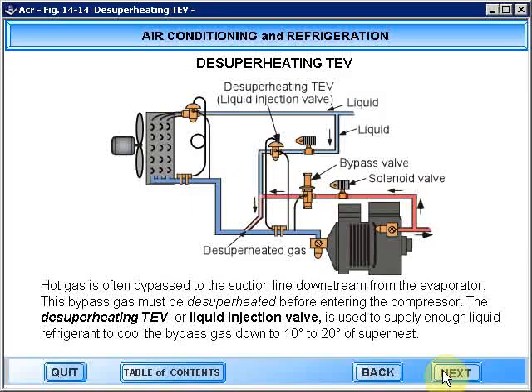Hot gas is often bypassed to the suction line downstream from the evaporator. This bypass gas must be desuperheated before entering the compressor. The desuperheating thermostatic expansion valve, or liquid injection valve, is used to supply enough liquid refrigerant to cool the bypass gas down to 10 to 20 degrees of superheat.